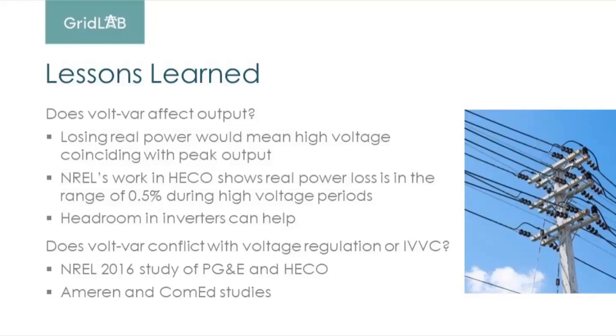And so we really wanted to look at some of the concerns that folks have raised about these different approaches, like volt-var and volt-watt. A lot of folks are concerned about whether volt-var really affects output. If I'm asked to turn on volt-var regulation and help regulate and mitigate voltage impacts on the distribution circuits, is that going to mean that I'm going to lose real power production? For you to lose real power, two things would have to happen, right? You need to be running at high voltage, and you need to be running at full output. Because if you're not running at full output, you have headroom in the inverter to produce reactive power.